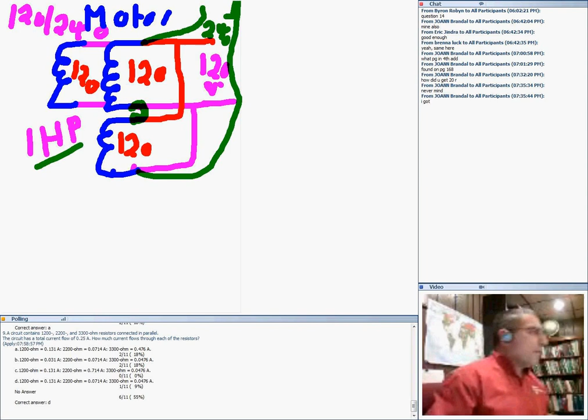Generators can do the same thing. Let me show you phase - a three-phase delta motor is easy. Here's a three-phase delta motor, and it comes from the manufacturer with 3 coils, 3 windings each. Let's say each coil is actually a 240 volt coil - this coil is 240, this coil is 240, and the last one is 240.